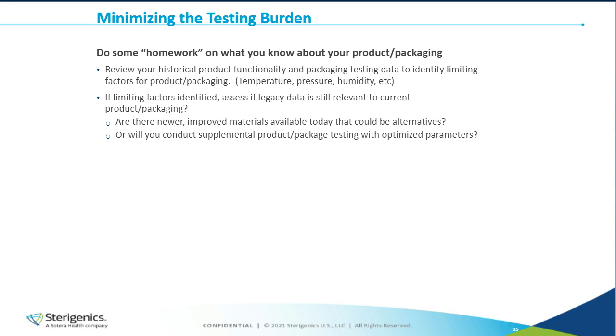So we need to review the history for product functionality, and based on the original parameters, you can define the threshold values and the maximum values for temperature, pressure, humidity, and so on, so that we know if we have a margin or a bit of buffer to play with. It's important to know whether all the activities that were done before are still relevant, and we can review them. But if we are changing materials, or other critical parameters that can have an impact on the bioburden or on the absorption properties, it has to be revised as well.